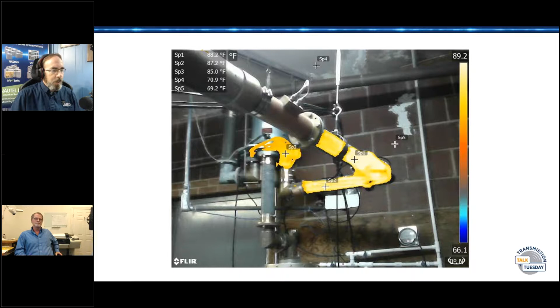Moving forward, electrical connections - this is an ongoing thing. If you've got a compression connection, and anytime you have stranded wire going into something that needs to be tightened down, you need to go in on a regular basis and check it out. This is why - right here. We ended up having to rob another old decommissioned CCA for a lot of parts due to that one. It went down, and it didn't take long when we opened the back door to figure out, yeah, we have a problem.